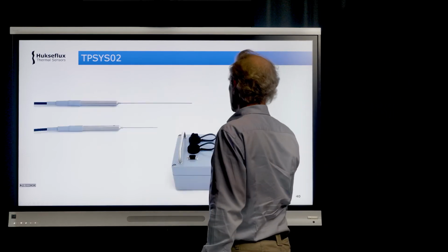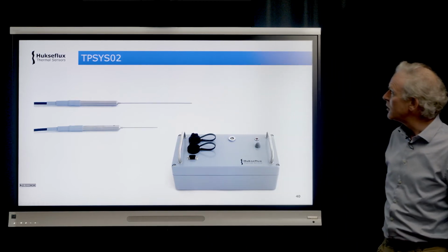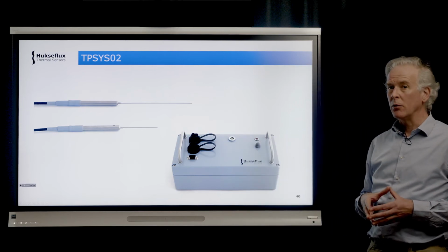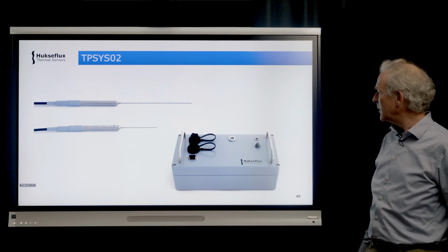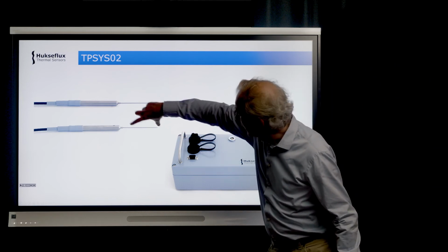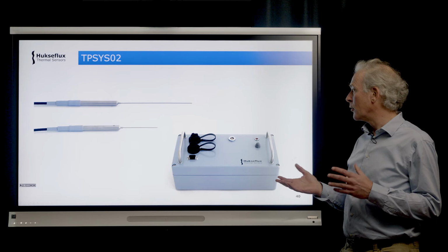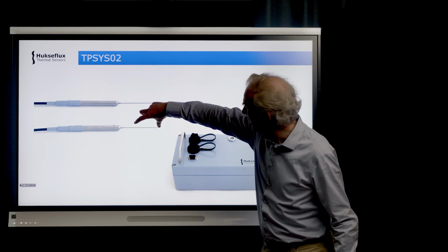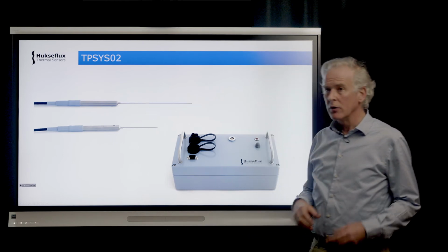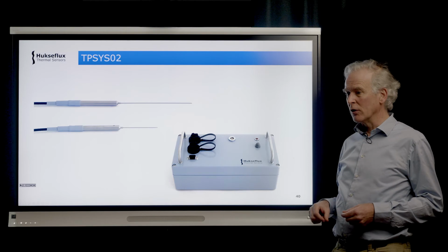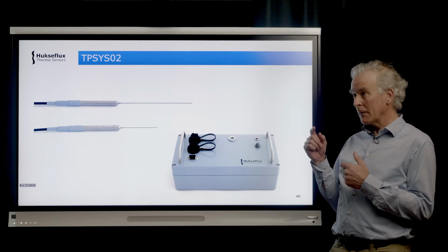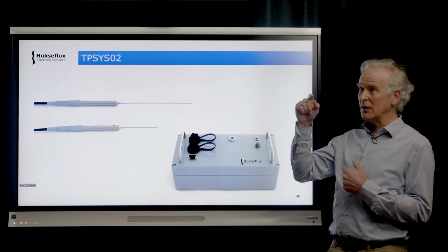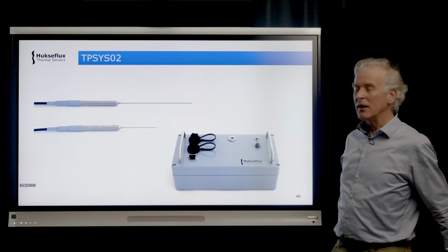We also have other systems, TP-Sys. They have very thin needles, about 1 millimeter, 1.6 millimeters. Also the needle length is smaller. On the order of 60 millimeters length is needed here as a minimum of insertion. The previous MTN needle was 100. The FTN was 170 millimeters.